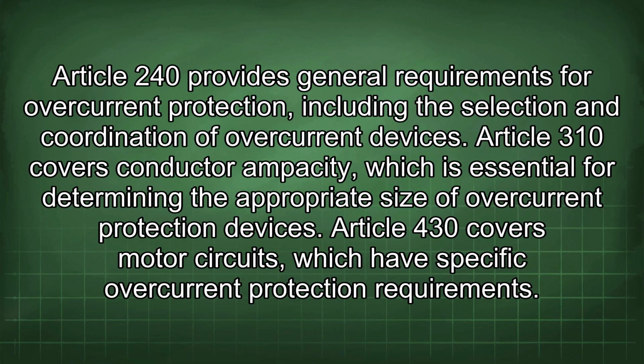Article 240 provides general requirements for overcurrent protection, including the selection and coordination of overcurrent devices. Article 310 covers conductor ampacity, which is essential for determining the appropriate size of overcurrent protection devices. Article 430 covers motor circuits, which have specific overcurrent protection requirements.